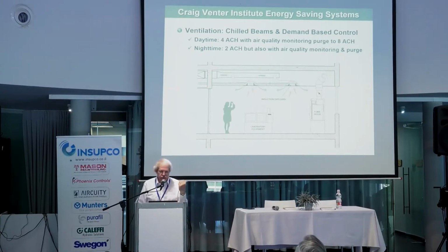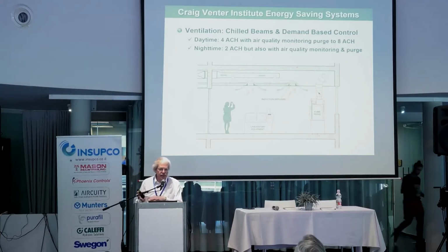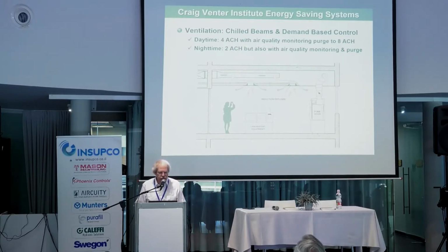Demand-based control, which is sort of the Aircuity system, is a common theme to get the air changes down. A critical aspect of these facilities is they tend to work with lower air change requirements. So it may be a demand-based control system, or maybe they've done some control banding or other means to try to reduce the air change requirements. In this approach, they're using 4 air changes during the day, 2 air changes at night.